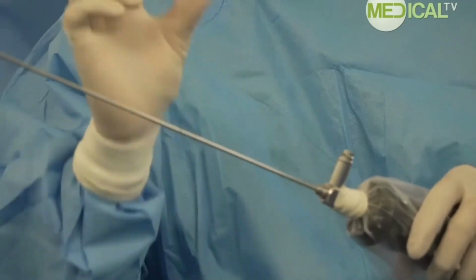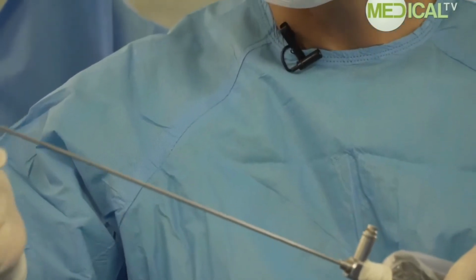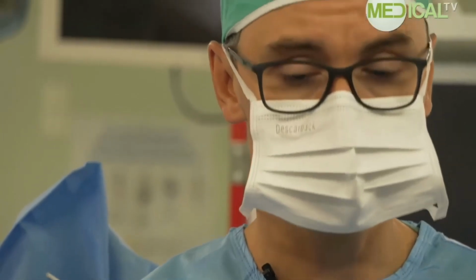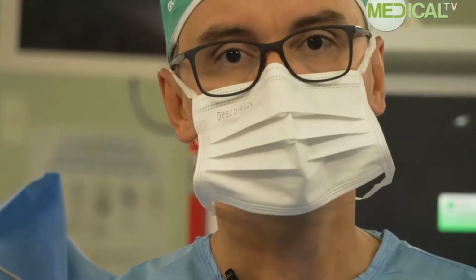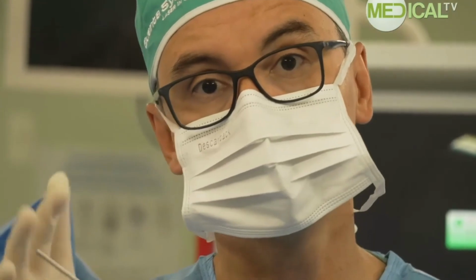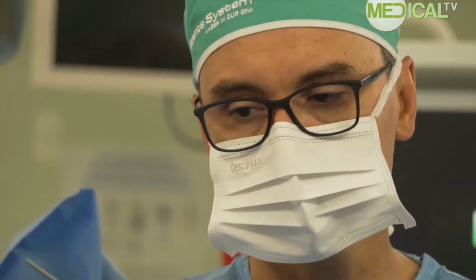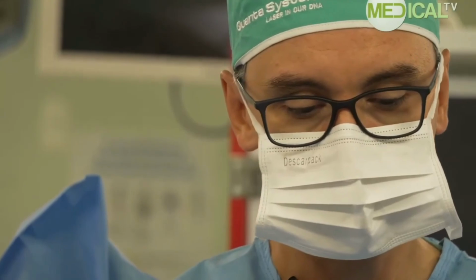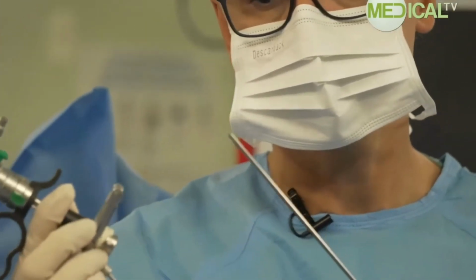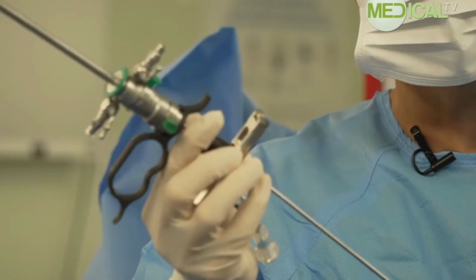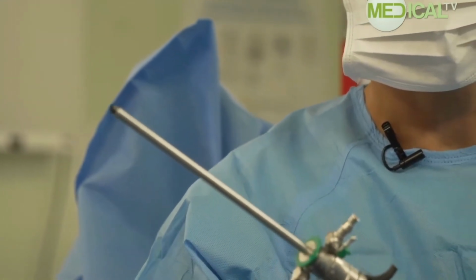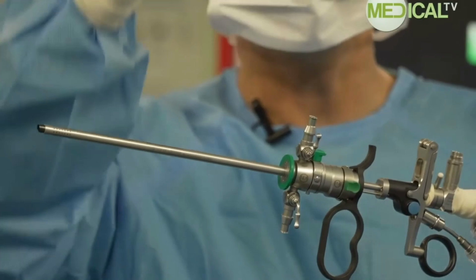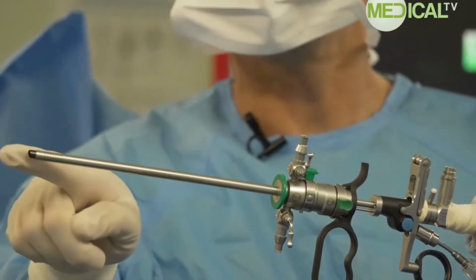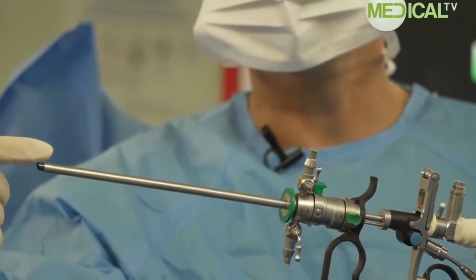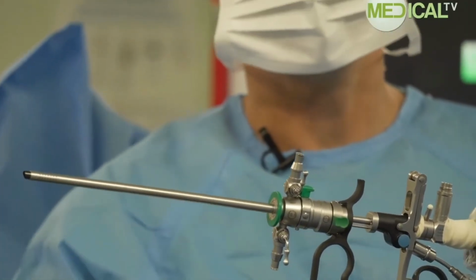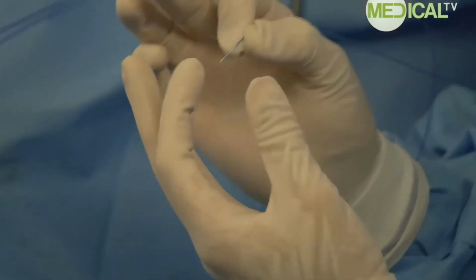MiLEP's instruments are distinct for their smaller caliber, notably the optics, a very thin tube, which measures 2.9 mm. There are a number of glass lenses inside, which enlarge the picture. Thus, due to the numerous lenses in close proximity, the image magnifies 20 times. And then on top we use the resectoscope, which has the working element, which is where the laser fiber is attached. And it features 2 small knobs. Through the middle of the device runs the serum inlet, while at the end, extremely tiny holes allow for the disposal of serum. All the energy from the laser passes through this optical fiber.